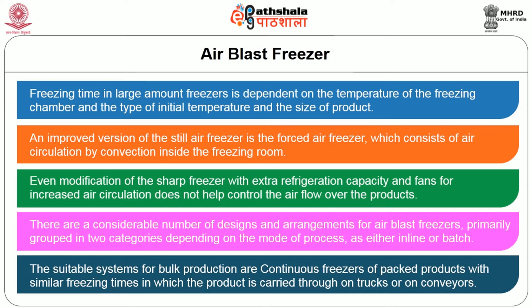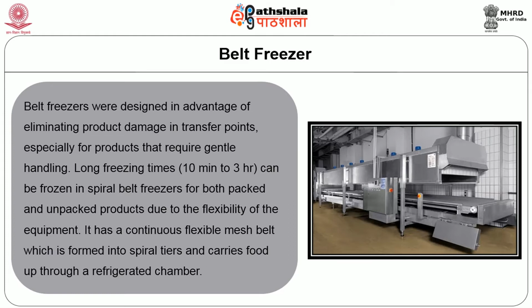Belt freezers were designed with the advantage of eliminating product damage at transfer points, especially for products that require gentle handling. Long freezing times can be handled in a spiral belt freezer for both packed and unpacked product due to the flexibility of the equipment. It has a continuous flexible mesh belt which is formed into a spiral tier and carries food up through a refrigerated chamber. Cold air or a spray of liquid nitrogen is directed down through the belt stack in a countercurrent flow, which reduces weight loss due to evaporation of moisture.